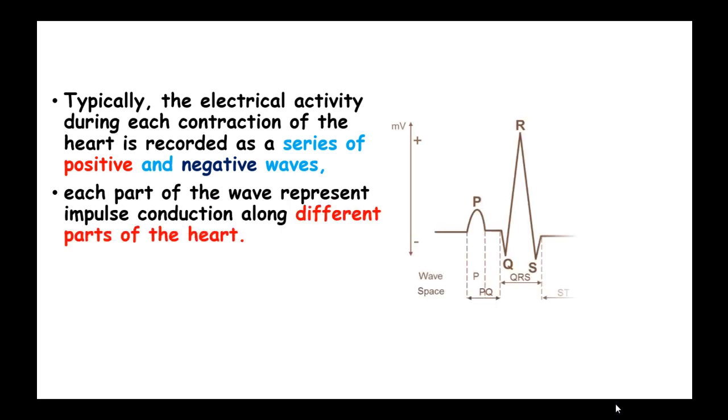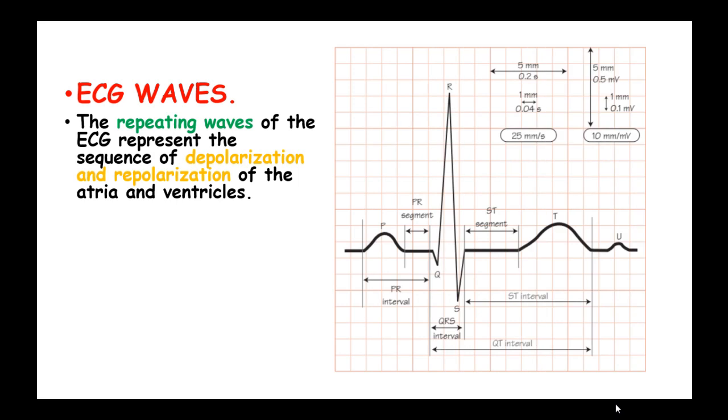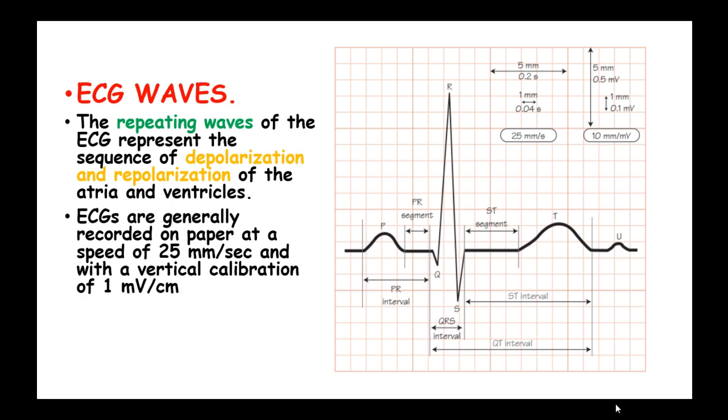Typically the electrical activity during each contraction of the heart is recorded as a series of positive and negative waves. Each part of the wave represents impulse conduction along different parts of the heart. The repeating waves of the electrocardiogram represent the sequence of depolarization and repolarization of the atria and the ventricles. ECGs are generally recorded on paper at a speed of 25 millimeters per second and with a vertical calibration of 1 millivolt per centimeter.